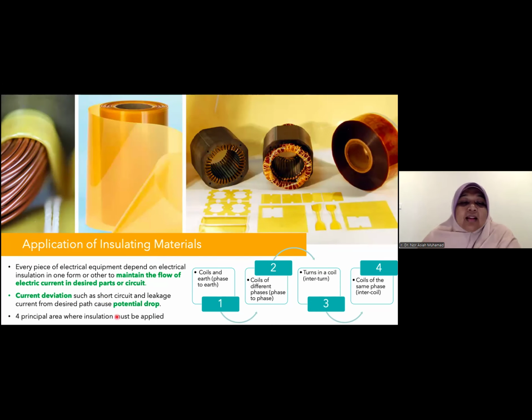So we want to avoid short circuits or leakage current that will cause a potential drop. So there are four principles of insulation material application. First, we will insulate between the coil and the earth. So in high voltage or electrical equipment, there are conductors. They will be in the form of a coil or a straight wire. So we want to isolate between the coil and the earth. So we call it phase to earth.